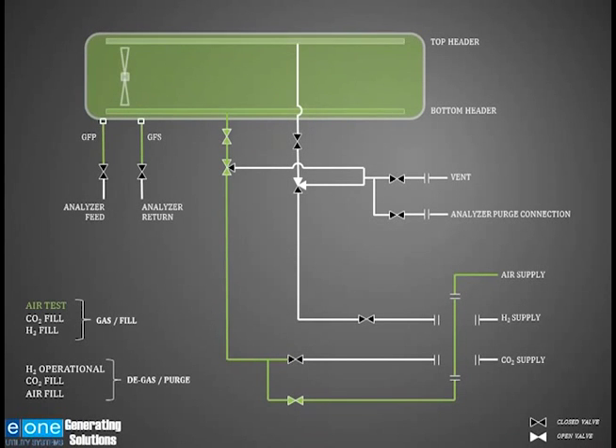And when the generator is filled with air and pressurized, we close off all the valves to run our air test. Now over on the left-hand side, where you can see where the analyzer connects, that also is where the case pressure gauge is connected. So one of those valves may be open during this point to monitor the air pressure in the generator during this test. Once not only the generator has passed the air test, but the gas manifold has passed the air test also, now we want to put CO2 into the generator.